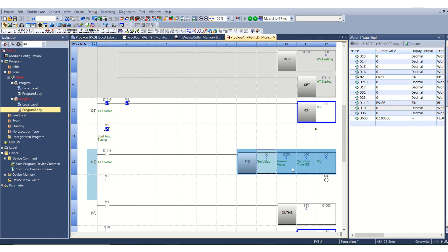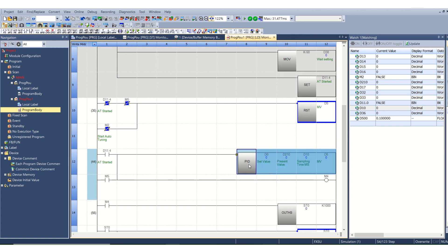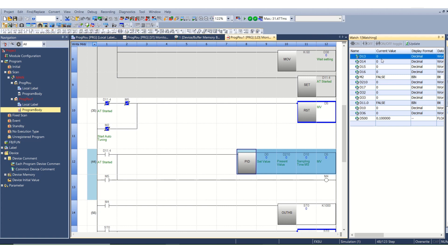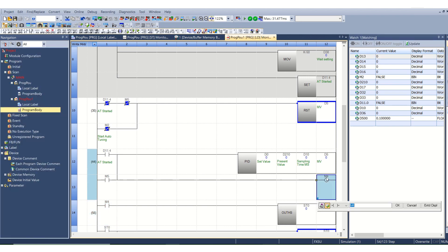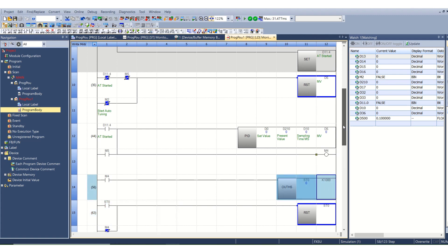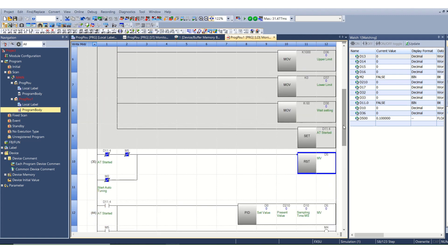Initially these values are 0, and once we autotune this PID function the value will automatically generate according to your response of the heater we are using. I have used M4 as autotuning running indicator. I have used a timer with the cycle time of 1000.